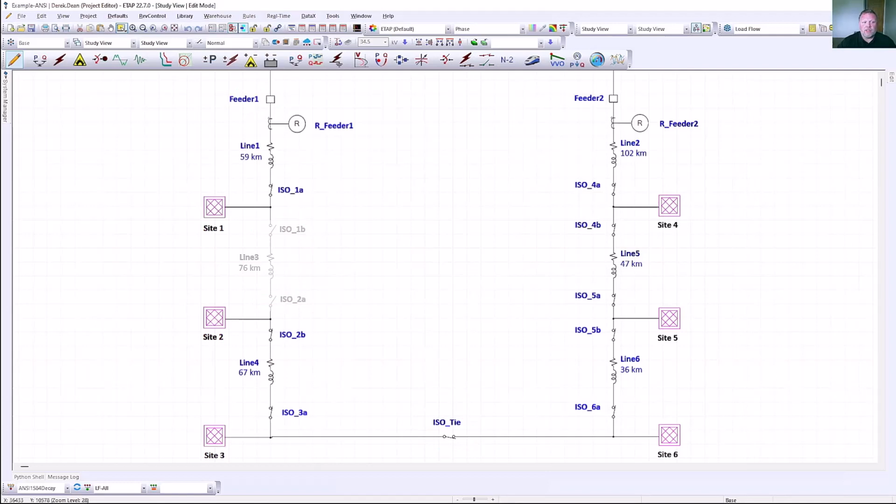These steps can be executed manually in the field, manually executed by an operator through the SCADA, or automatically executed through the ETAP fault location solution. It is important to note that in more complex scenarios, the isolation and restoration steps may not be as apparent, and the switching optimization engine can help determine the most effective steps to restore production while minimizing downtime. In summary, the ETAP fault location solution can help quickly identify the fault location and provide recommendations for isolating and restoring power, resulting in reduced downtime and improved efficiency.